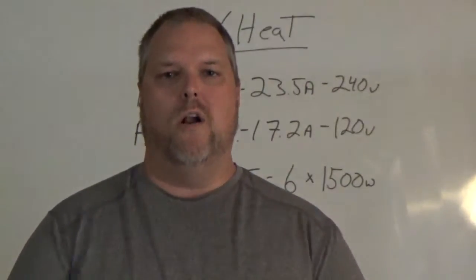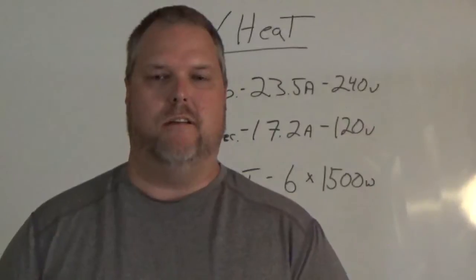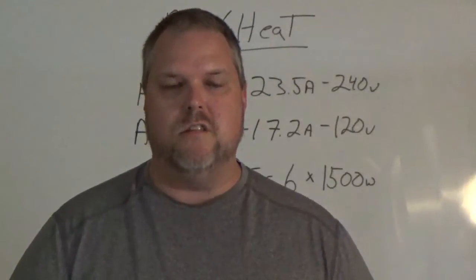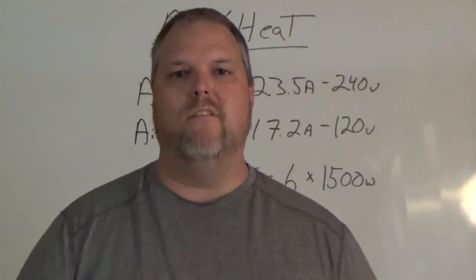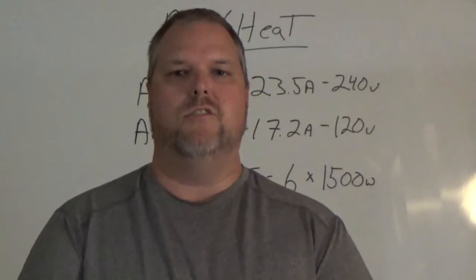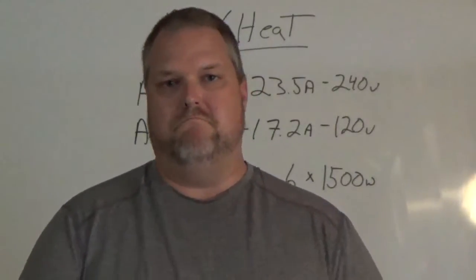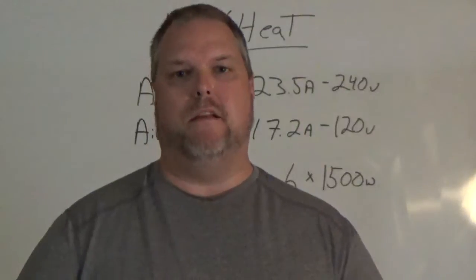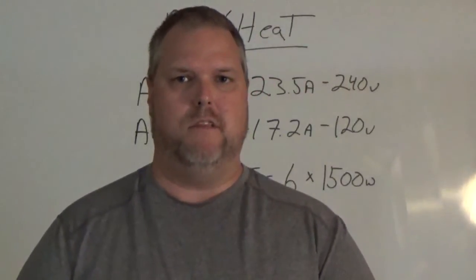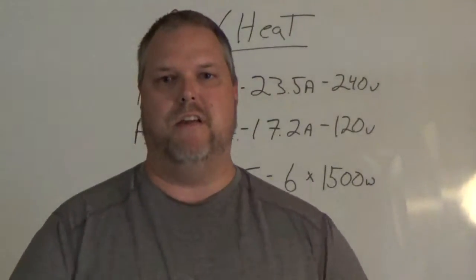What does it even mean? Well, we have to think about what we're going to use that we will not be using at the same time: heat and air conditioning. Article 220.60 tells us that non-coincidental loads basically states that whatever we determine to be the largest, that's what we use in our calculation. Depending on the part of country you live in, heat may override your air conditioning. If you live down south, air conditioning may be larger than your heat. Remember, we're not going to run heat and air conditioning at the same time, so let's not calculate for it.